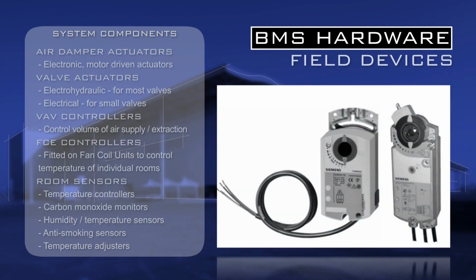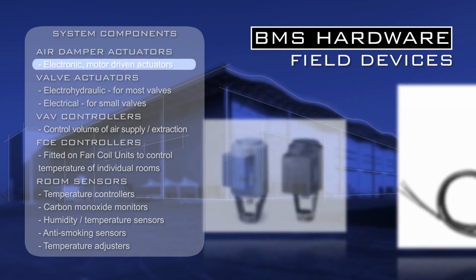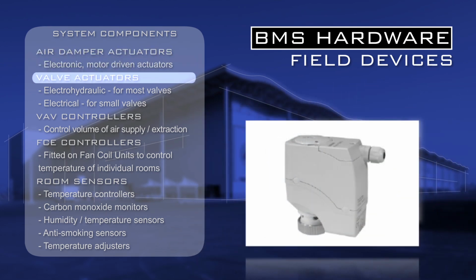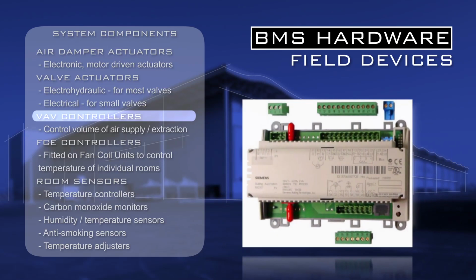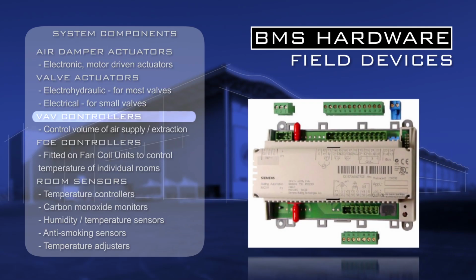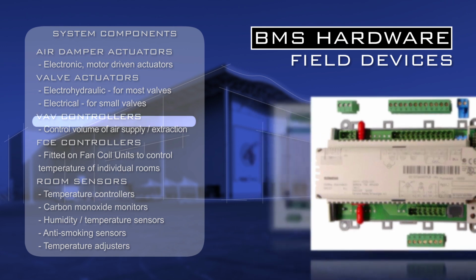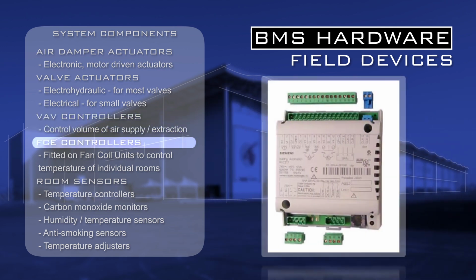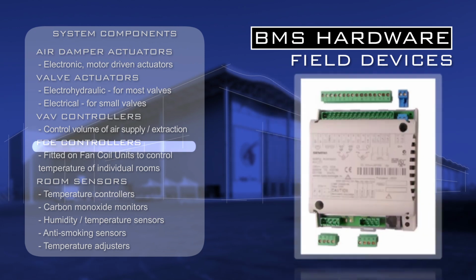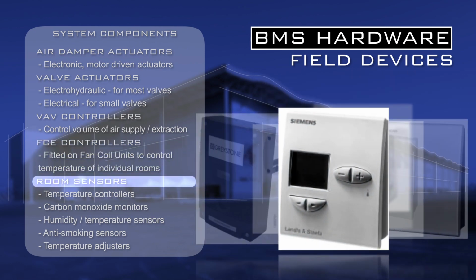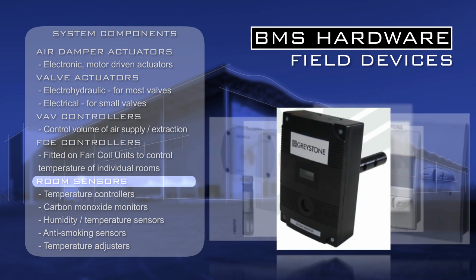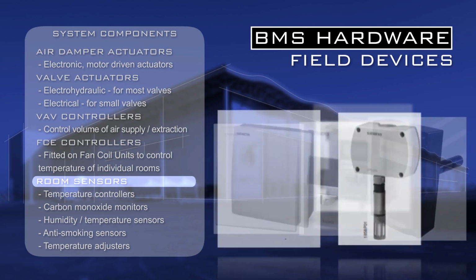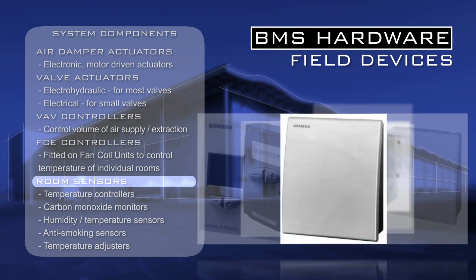Field devices comprise air damper actuators, which are electronic and motor-driven. Valve actuators. Most valves are electro-hydraulic. Small valves, though, are electrical. VAV controllers, which control the volume of the air supply and extraction. FCE controllers are fitted on fan coil units and control the temperature of individual rooms. There are also a number of room sensors, which are temperature controllers, carbon monoxide monitors, humidity and temperature sensors, anti-smoking sensors, and temperature adjusters.